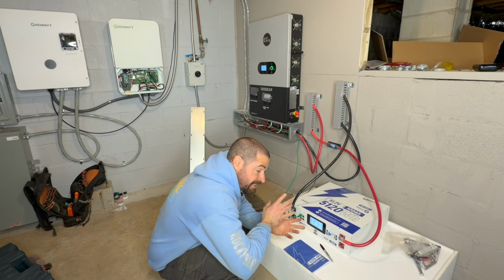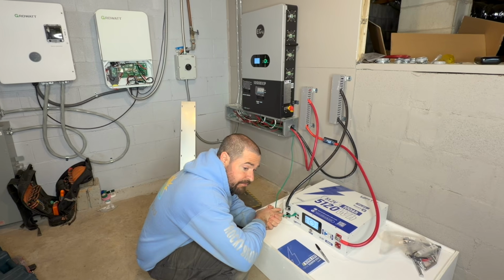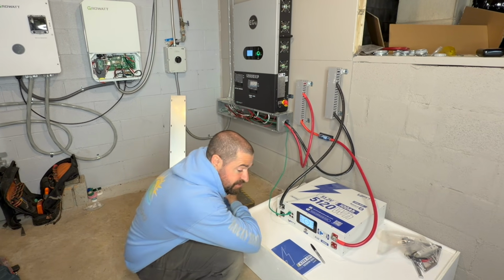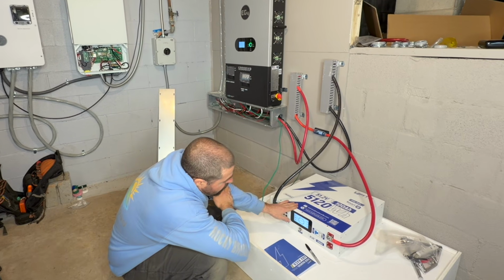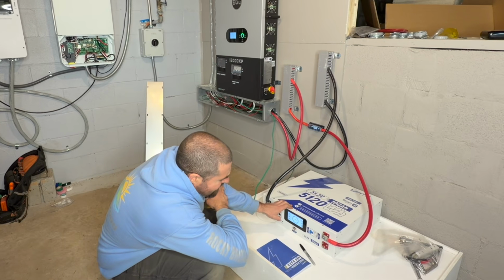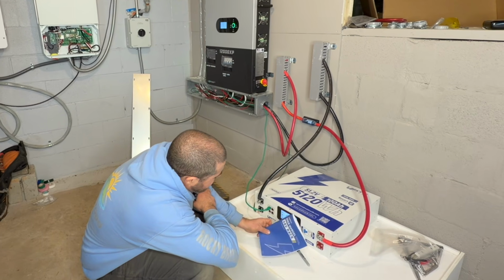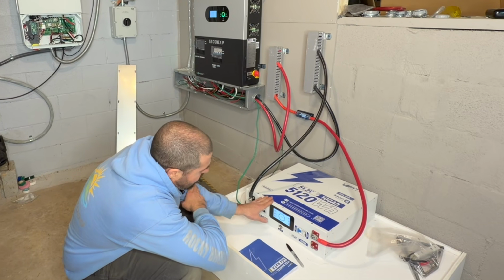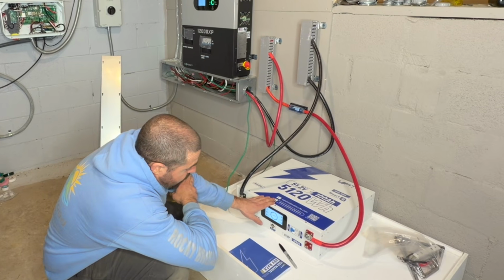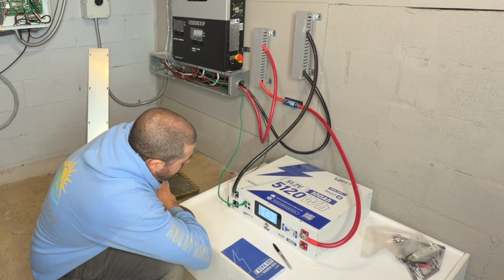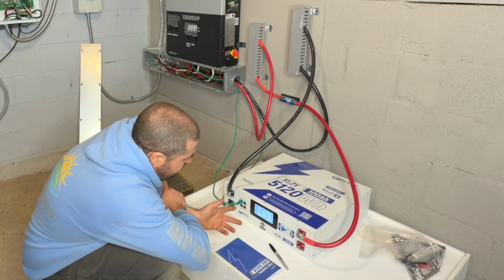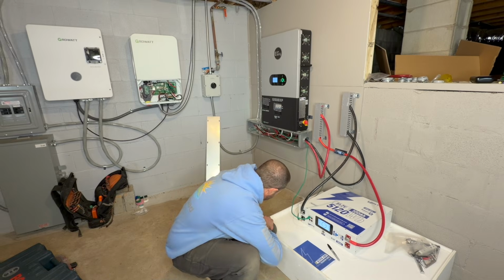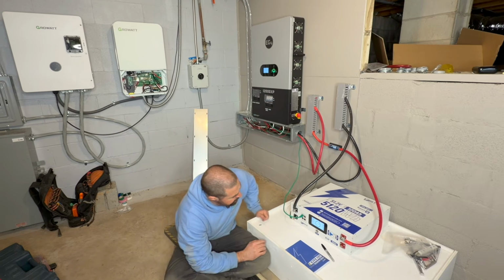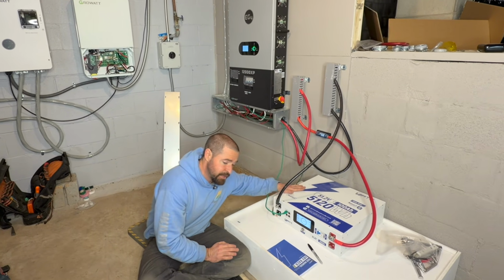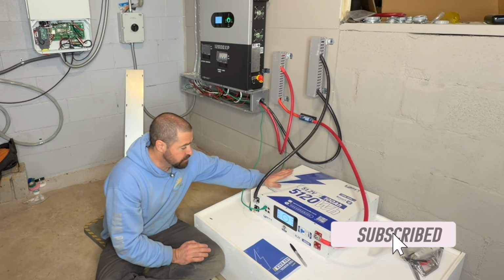Now, technically, if you were actually going to use these WattCycle batteries with the 12000 XP, the manual says to have a minimum of 400 amp hours. That would be 4 of these batteries. Each of these batteries has about 5,000 watts output, I believe. So in my opinion, you could probably get away with 3, but 1 is just way undersized. This battery is way too small to handle the output or the charging of that inverter. So I'm going to do my best here to set some parameters to limit any issues that could cause. Just so you're aware, I'm doing this to create content. If I were going to use a whole stack of these WattCycle batteries with this inverter, I'd probably at least buy 4 of them.